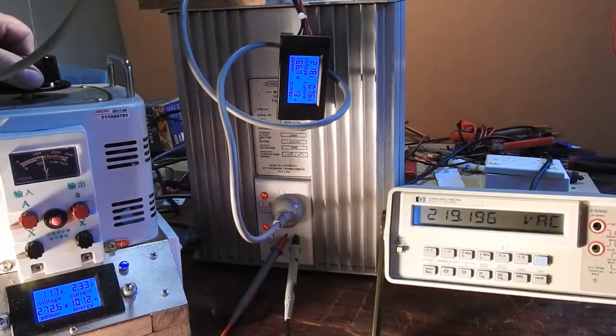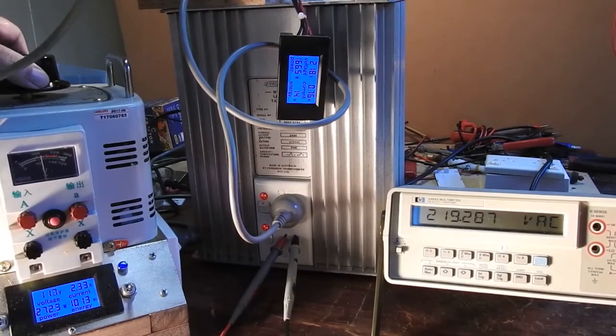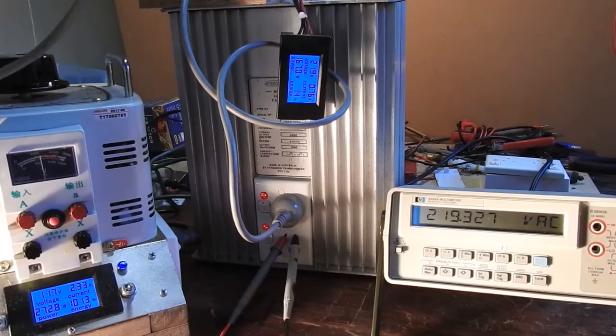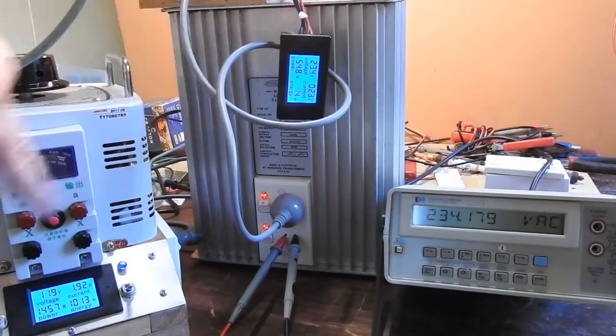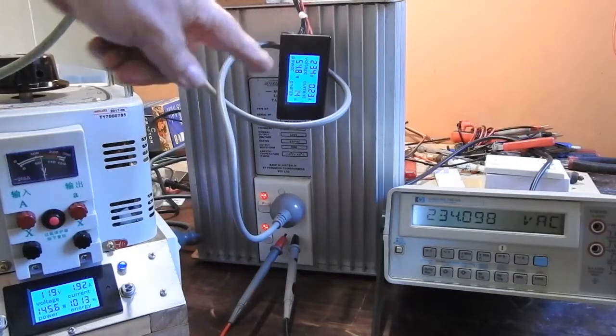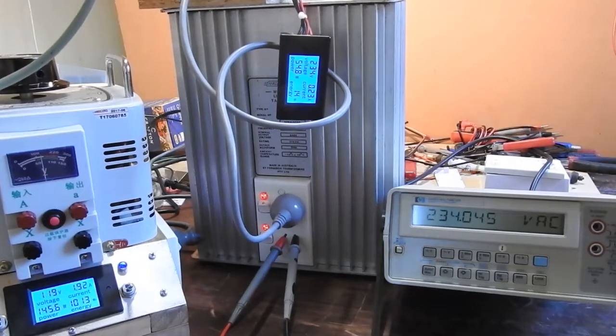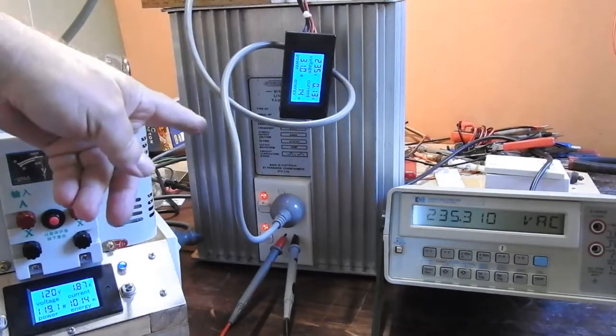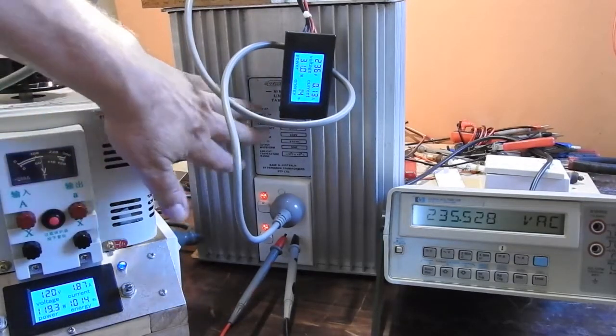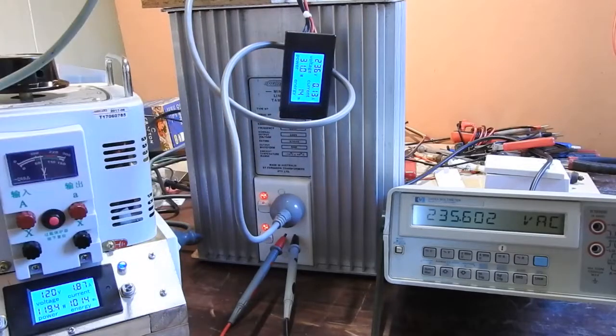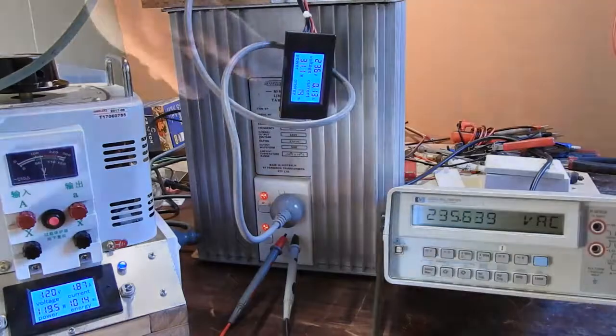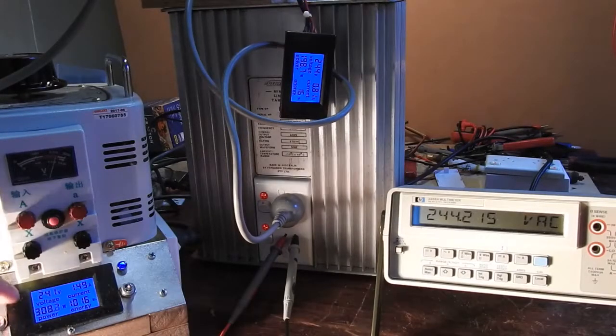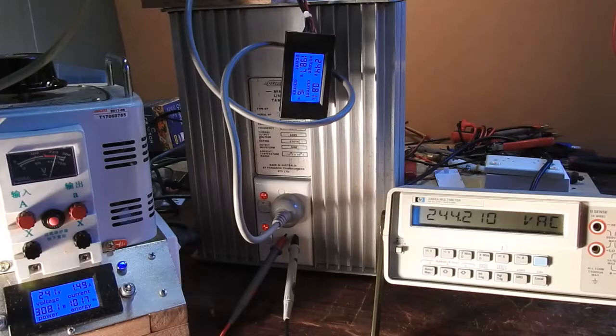167 out for 270 in, so we're wasting a good 100 watts in there. And let's just turn this big bulb off again. Now we're getting 145, 54. So maybe the losses are constant 100 watts up to the limit of this, which is rated at 275 VA, so you can't put much more load on it than what I am. 200 watts out, 300 watts in. Not very efficient, but I suppose now we should look at waveforms. But in terms of constant voltage, it certainly seems to be pretty good.